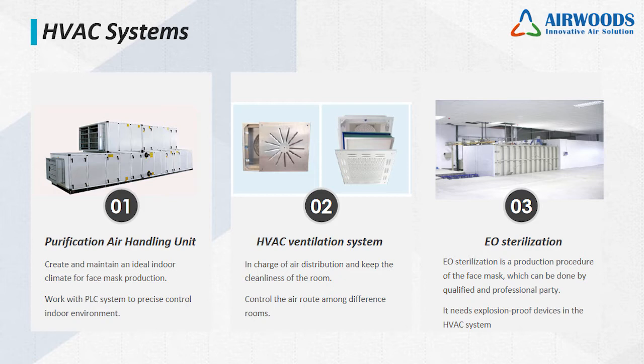So this last one is the EO sterilization. EO sterilization is a production procedure of the face mask, which can be done by a qualified and professional party. Inside the EO sterilization room, the HVAC system needs explosion-proof devices, like the fan motor, the light, electric components, and so on. And the exhaust air should be washed by water before being discharged outside.